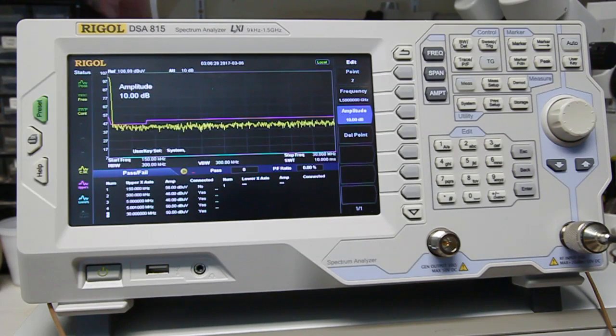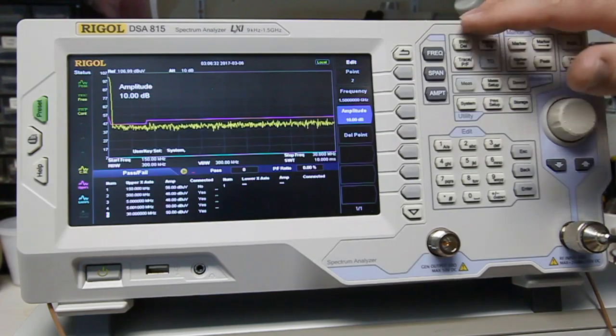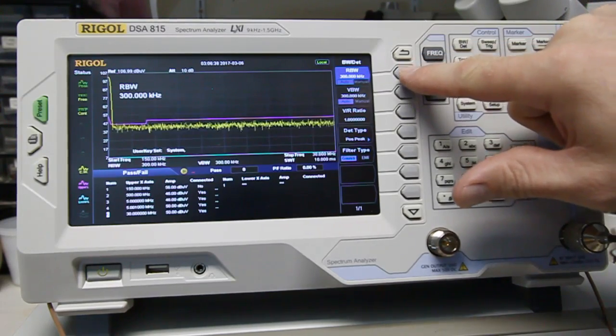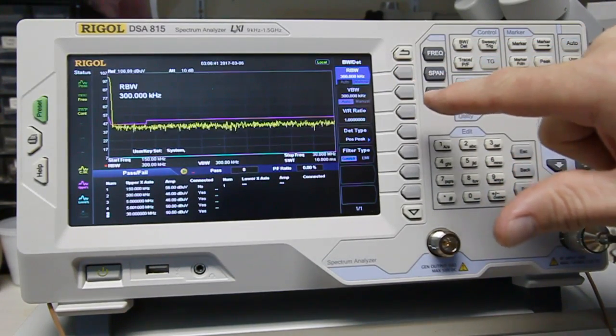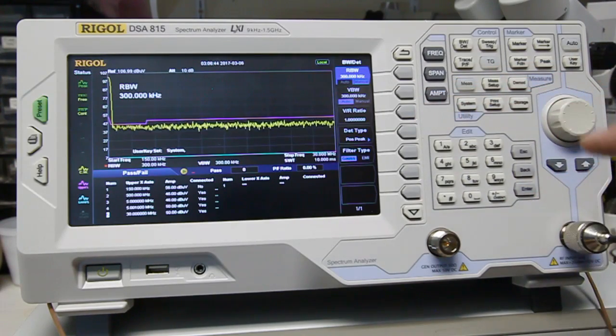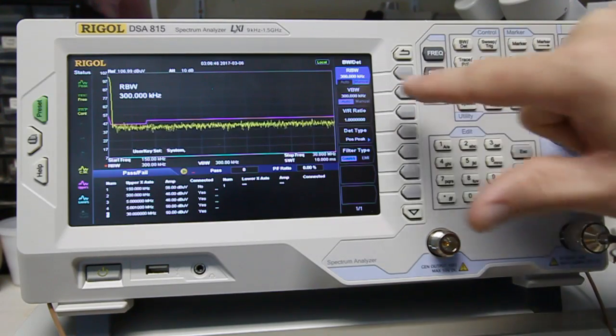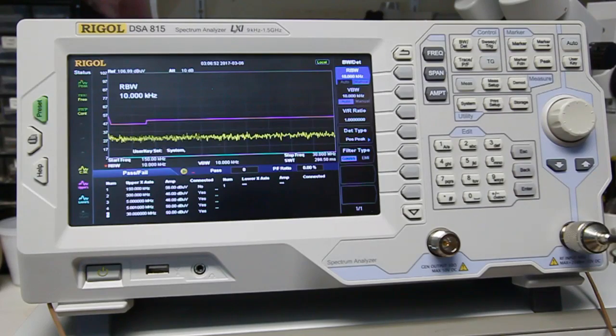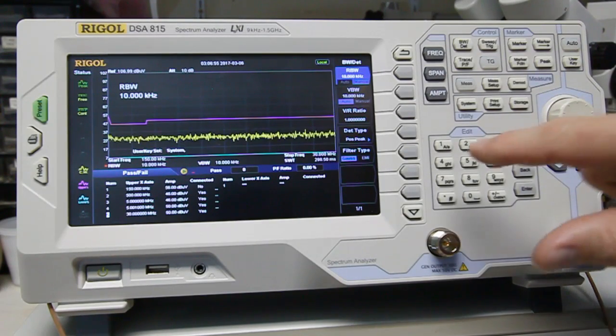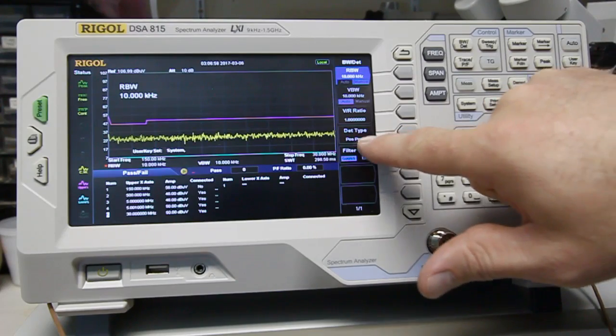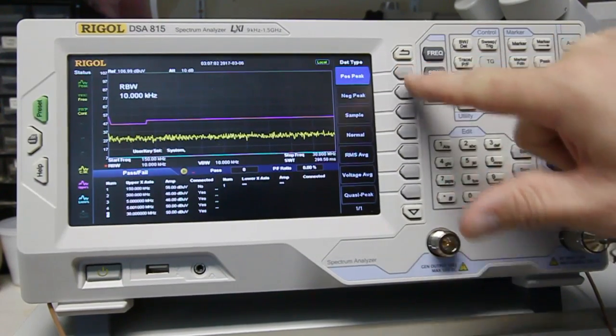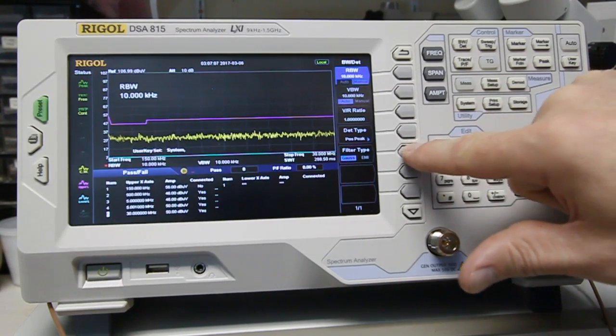Now we just need to do a couple more things for the analyzer. We're going to go into the bandwidth detector. And the RBW, per the spec, by EN55022, CISPR22, says that it should be 9 kilohertz. So RBW manual, I'm going to go to 9 kilohertz. And we should also make sure that the detector is in positive peak. Here's our settings. It is in positive peak. And let's go back to filter type. And we're going to go to the EMI for the filter type.